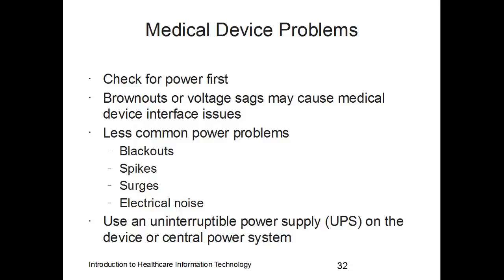Brownouts or voltage sags may cause medical device interface issues. Some less common power problems with medical devices: blackouts, spikes, surges, or electrical noise. So it is advised that you use a UPS, an uninterruptible power supply, on the device or on a central power system.